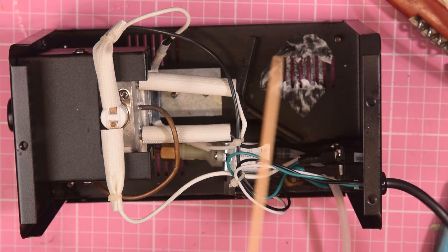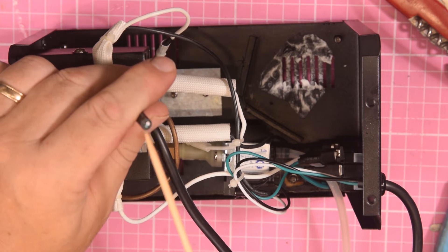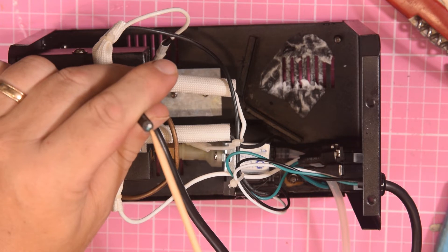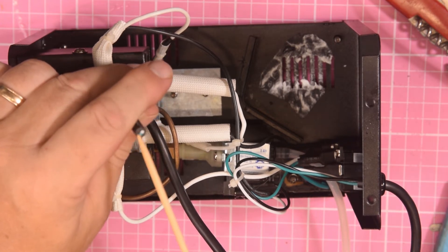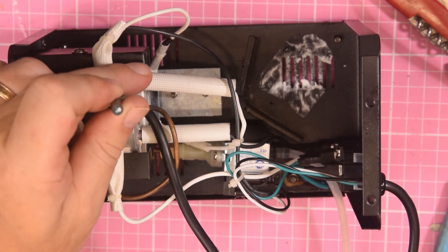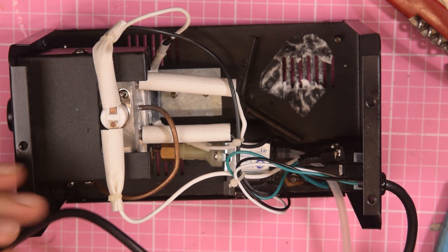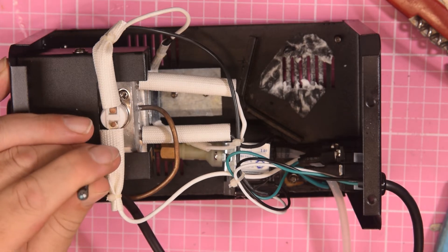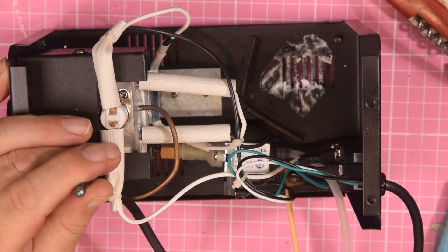This is the control wire - I've cut it off, and that's been done for a reason. I'm going to extend this cable because I think it's about seven meters and that's just not enough. I'm going to put a plug on each end and fit an extension lead in the middle so it's still usable.